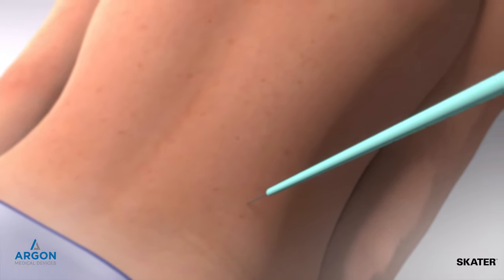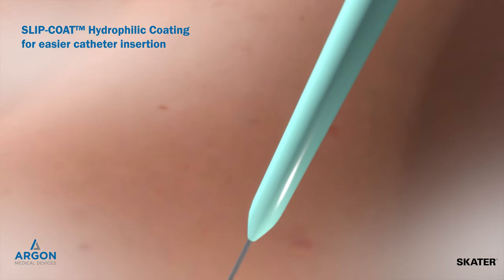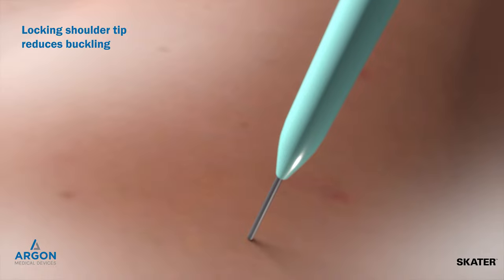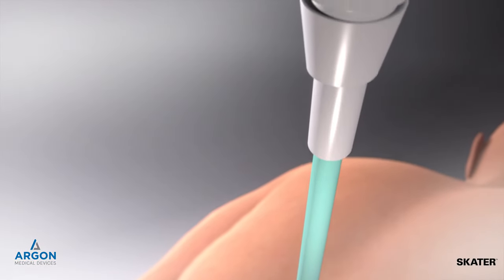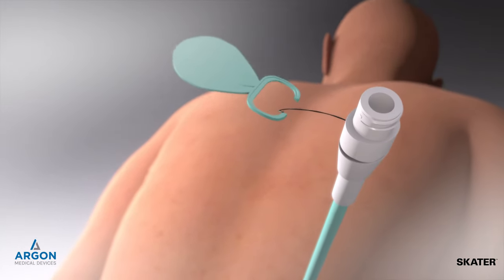Skater's Slip-Coat hydrophilic coating, activated with saline, significantly reduces friction for easier catheter insertion, while the locking shoulder tip also helps to reduce buckling. Position markers confirm catheter position after placement, and consistent catheter-to-hub inner lumen size prevents bottlenecking.